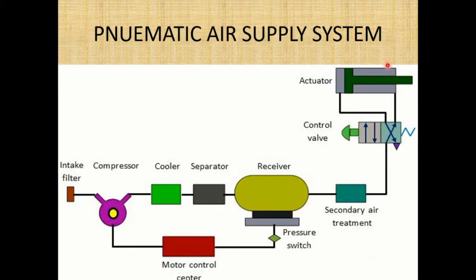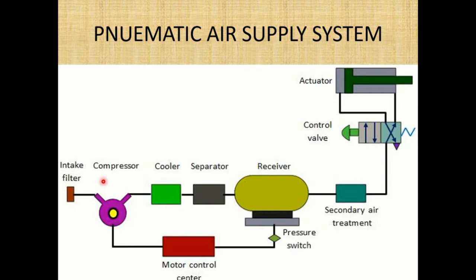Next comes the secondary air treatment system, which involves the control valve and actuator — to be discussed later. First, the inlet filter: it is required because atmospheric air carries a lot of dust material. The filter removes those dust particles before passing air to the compressor. The compressor is the heart of the pneumatic air supply system — it compresses the air, reducing its volume and increasing its pressure. Since temperature is directly proportional to pressure, as pressure increases, temperature also increases.